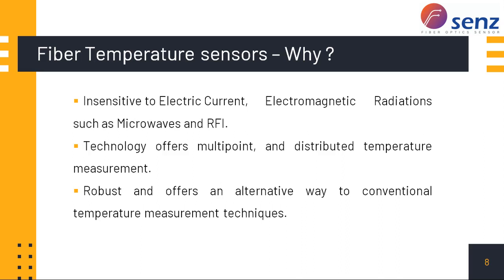So why, first of all, when we have so many types of temperature sensors, like thermocouples, RTDs, strain gauges, then infrared pyrometers or thermal imagers, why do we need a fiber temperature sensor? Applications where all of these would not work, we would need to go to fiber temperature sensors. The reasons are fiber is insensitive to electric current, electromagnetic radiation or radio frequency. So this is one area where if you put an RTD inside a microwave oven, it is difficult to protect the RTD from the microwave. So in such cases, such kind of fiber sensors may be useful. Or measuring inside a big transformer, there would be a lot of magnetic interference, and a normal RTD would not work.